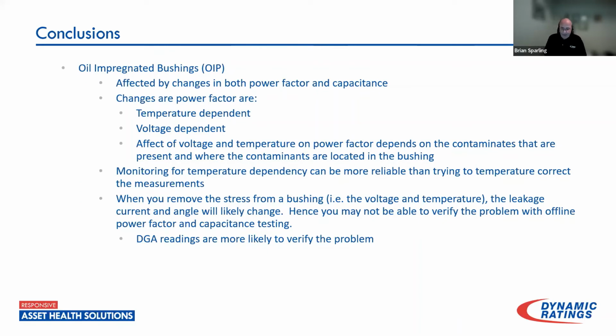So from a conclusion point of view, we have OIP bushings that are affected by both changes in power factor and capacitance. We know from this that changes in the dissipation factor are temperature dependent. They're also voltage dependent. Therefore, the effect of voltage and temperature on power factor depends on the contaminants that are present and where the contaminants are located in the bushing. Monitoring for this temperature dependency, as you saw, can be more reliable than trying to temperature correct the measurements. Don't try to do that. Just following the performance of the bushing in service is going to give you a lot more information about the health and condition of that bushing.